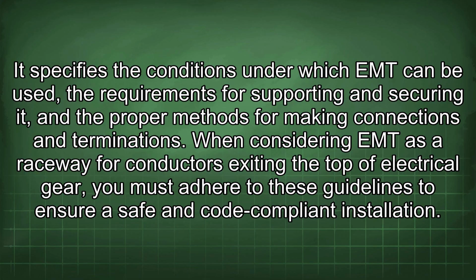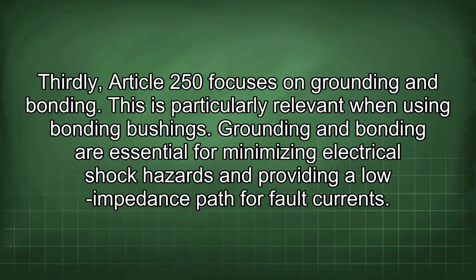When considering EMT as a raceway for conductors exiting the top of electrical gear, you must adhere to these guidelines to ensure a safe and code-compliant installation. Thirdly, Article 250 focuses on grounding and bonding. This is particularly relevant when using bonding bushings. Grounding and bonding are essential for minimizing electrical shock hazards and providing a low impedance path for fault currents.